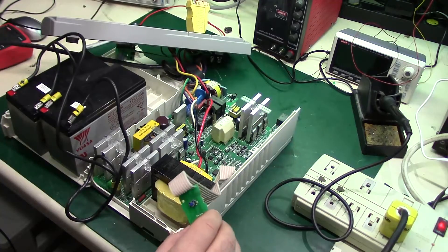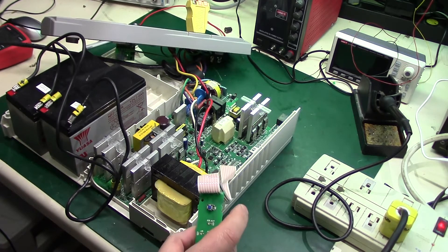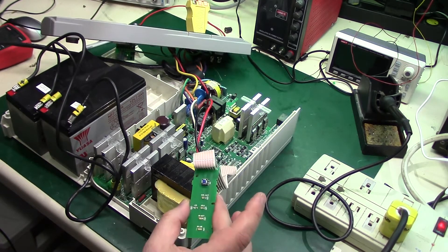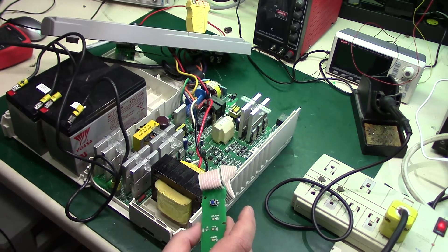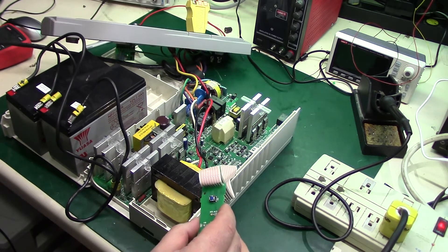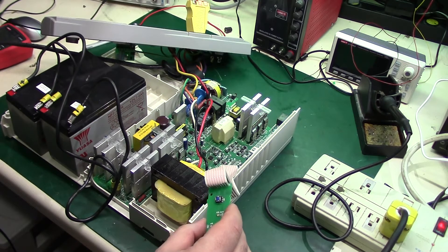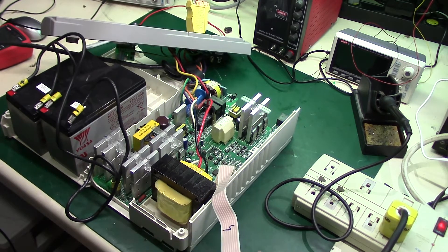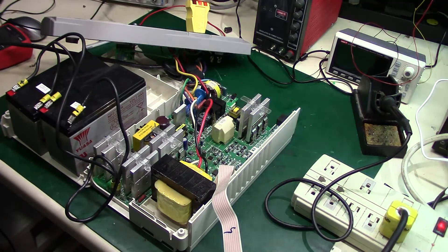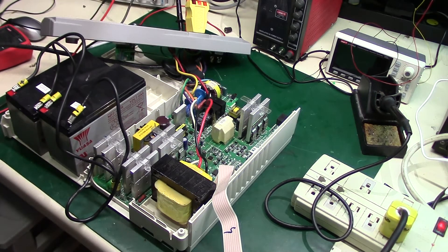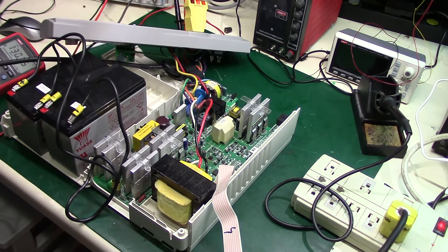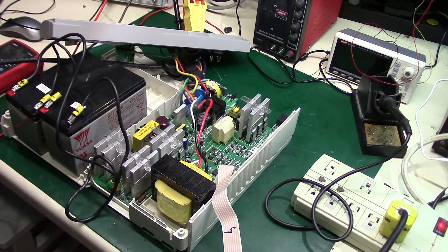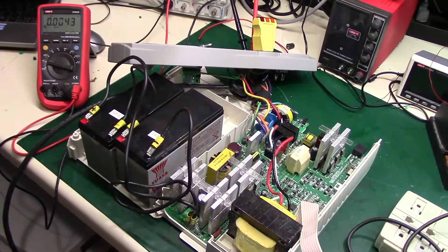Okay, mains is on. See, at least it turns on this time. That's kind of a big difference. And you can see that mains is actually going to my test plug. I don't know if that'll show illuminating on camera or not. But then once it does, it goes to inverter mode and it doesn't come out. And we're showing 130 volts out on the multimeter, which is kind of way too high. Way too high. It should not be that high.